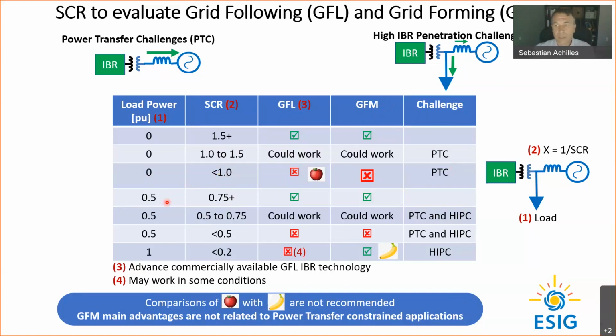Now, if we start looking at scenarios where the load is different from 0, we're actually not transferring all the power through this reactance. We will find that with a load of 0.5 per unit, short circuit ratios well below 1 are stable even with grid following and grid forming. As we continue to reduce the short circuit ratio, we will find some conditions where this may or may not work. And then if we push the short circuit ratio such that the steady state condition is not feasible, both of the concepts, grid following and grid forming, are unstable.